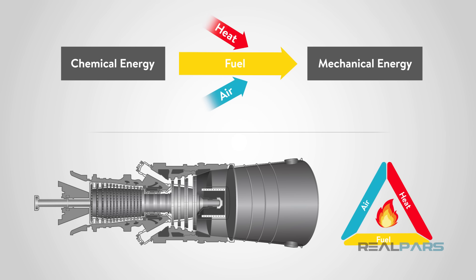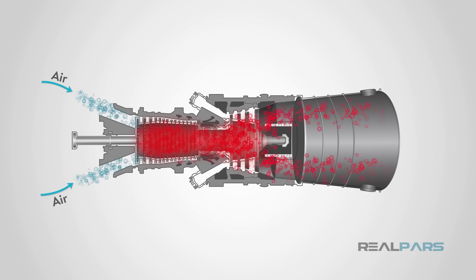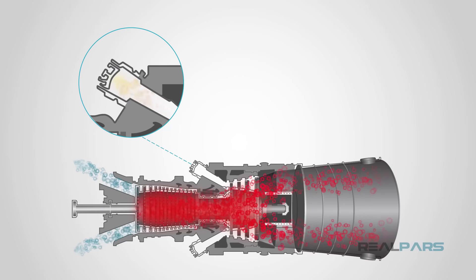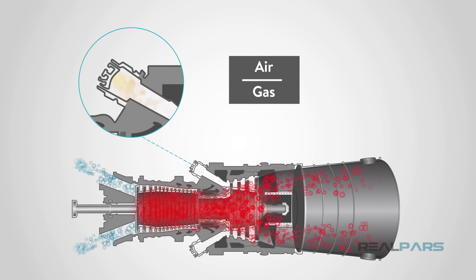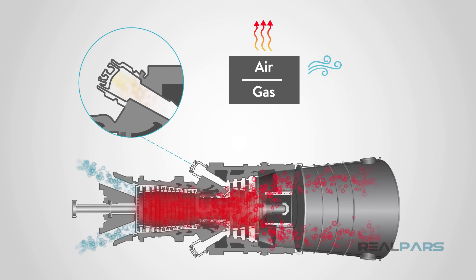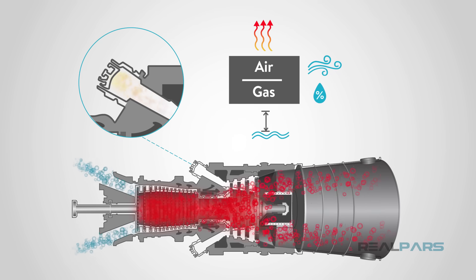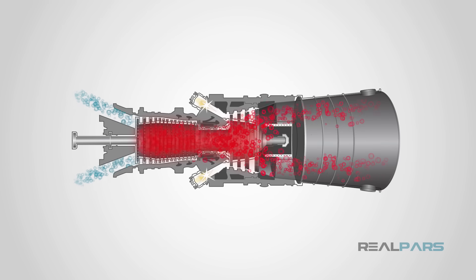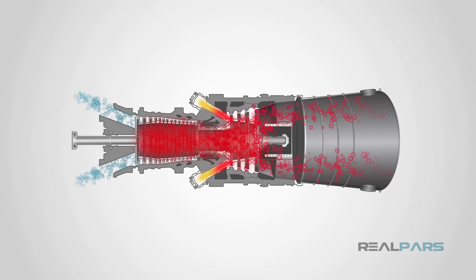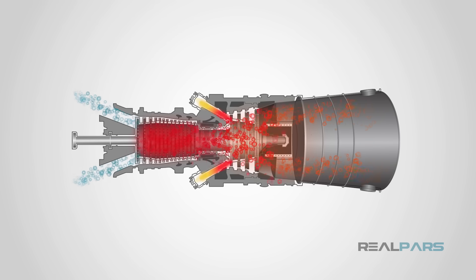Air is let into the gas turbine through an air intake and mixed with a proper amount of natural gas. The air-gas ratio is determined based on the specific heating value of the gas and quality of the air, amount of moisture, altitude from sea level, and so on. An ignition system then makes the initial sparks, whereby heat is provided. When the fire is established and stabilized in the combustion chamber, the ignition system will be put out of service.